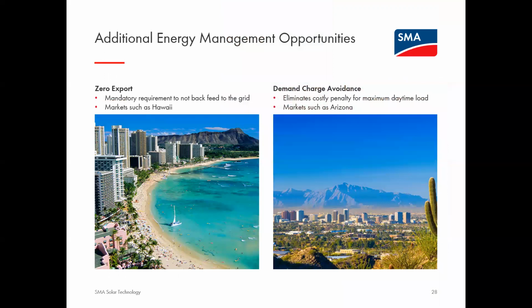Additional use cases that the SMA Energy Storage Solution addresses: zero export. Important in markets like Hawaii, where utilities basically don't allow you to feed anything back into the grid. But it's also really interesting using zero export in markets where formal net metering policies don't exist, or maybe even in markets where you have a buy all, sell all condition. These exist in local municipal utilities and co-op utilities, sprinkled all around the U.S. So by operating your PV plant with a battery performing pure self-consumption, you can oftentimes avoid buying expensive electricity from the utility.